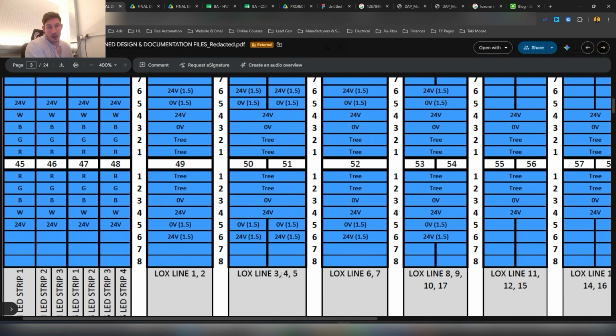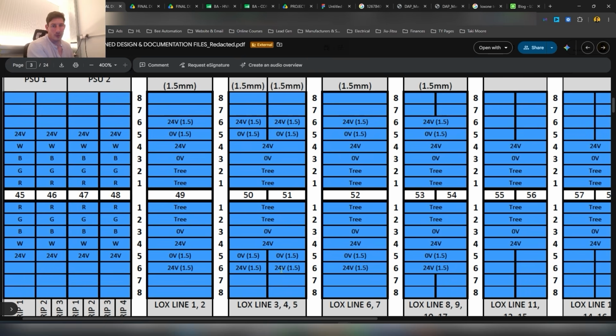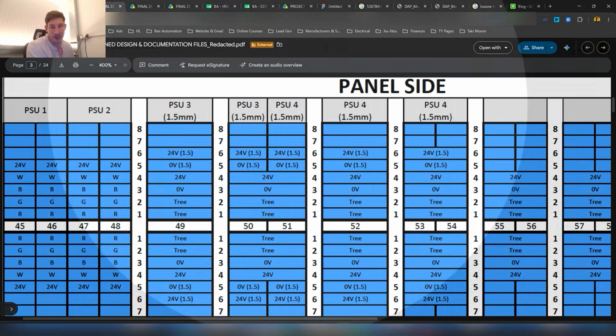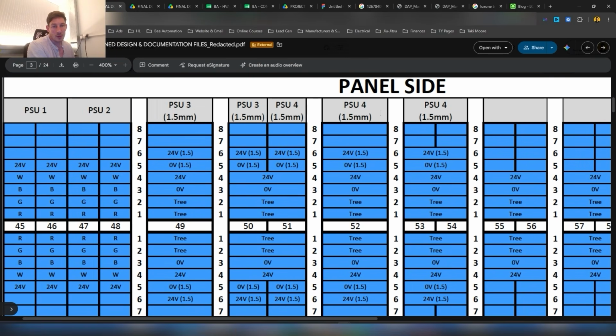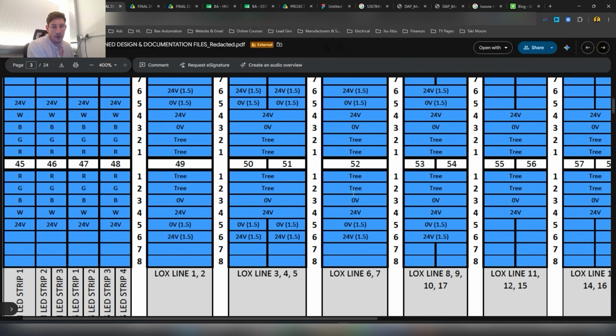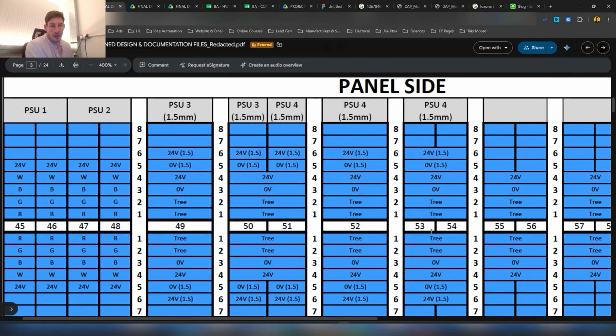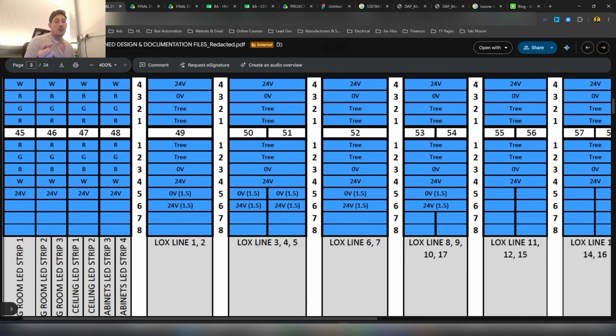This is where it gets a little bit difficult to explain. You can see PSU4, the 1.5 mil cable, so this 10 amp power supply is providing power to these terminals as well, 52, 53, 54. We're looping over and providing power to LOX zones 6, 7, 8, 9, 10 and 17. We're doing our power calculations to make sure we can do this without an overcurrent. We've done all our calculations, and it's just a clever way of distributing power while also distributing the comms from the Loxone tree extensions in a slightly different way.